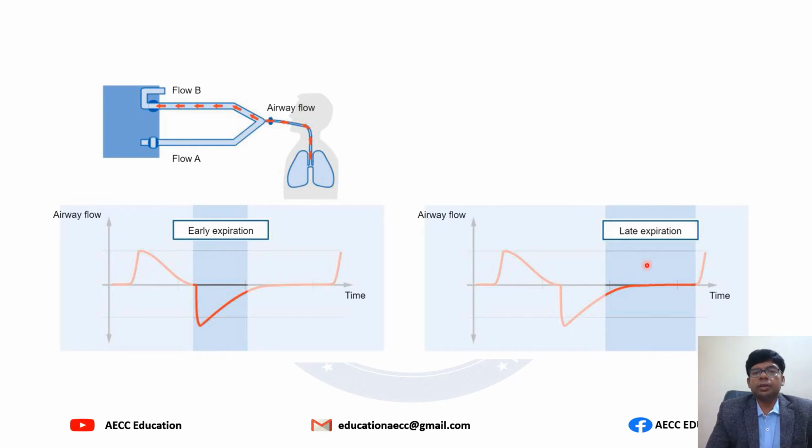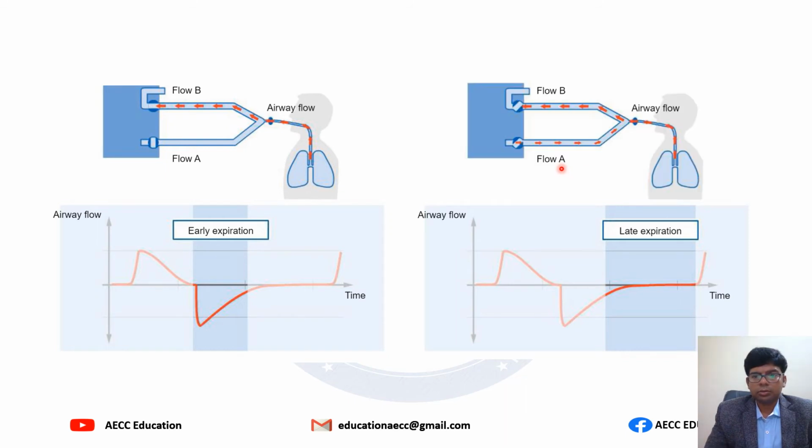In the late expiration, the ventilator tries to rebuild and maintain the set baseline pressure by reducing the expiratory valve opening for a high resistance against the expiratory valve and by opening slightly the inspiratory valve for a constant base flow, which is crucial for flow triggering.